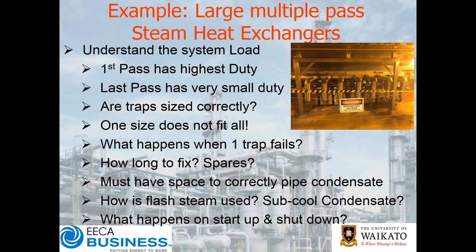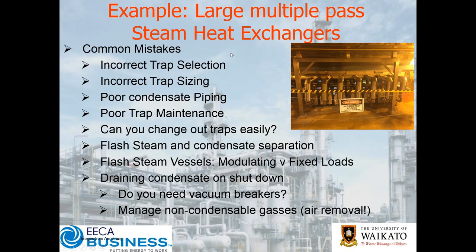The number one thing here is we must have the space to correctly pipe the condensate, unlike in that picture. The extra separate questions are: how are we going to use our flash steam — are we going to sub-cool the condensate? And very importantly, what happens on startup and shutdown? Common mistakes we often see include: incorrect trap selection, incorrect trap sizing, poor condensate piping, poor trap maintenance, can you change out the traps easily, getting good separation between flash steam and condensate, do we have a flash steam vessel, and with modulating versus fixed loads — all points we've covered in the flash steam webinar.